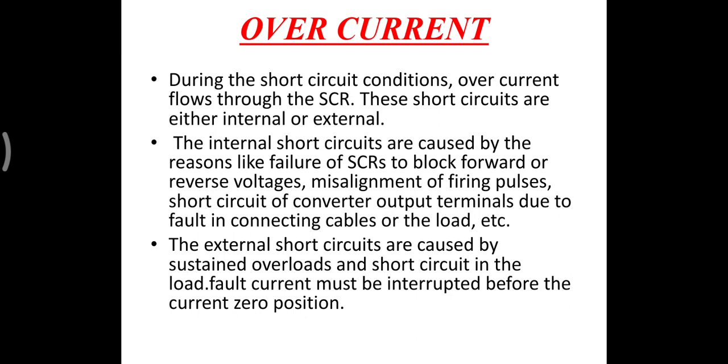The fault current must be interrupted before the current zero position. So the overcurrents are of two types. One is internal overcurrent and the second one is external overcurrent. Internal overcurrents are caused because of the failure of the SCR. That means misoperation of the SCR, or the blocking mode has failed in the SCR. In that situation, these internal short circuit currents are generated.